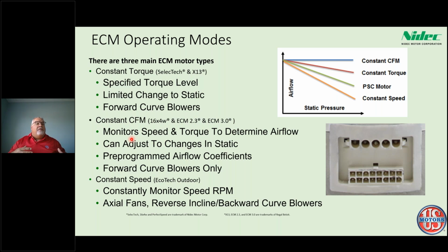As you can imagine, for an OEM to program one of these motors, they literally have to take the furnace or the blower or the air handler to an air chamber, and at that air chamber they're basically going to control the static pressure, measuring airflows, monitoring speed and torque, so they know at a specific CFM with this specific size unit it's going to have this much torque and speed to produce that CFM. So they'll mark that point, then they'll make some adjustments and they'll find other points along a curve. Once they have that down, they can go in and program that motor.